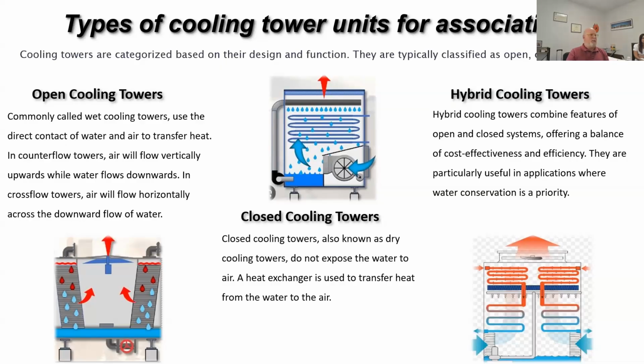It's well beyond the scope of this seminar to discuss the pros and cons of either. Short of that, if you're changing from a cross flow to a counterflow or counterflow to cross flow, it's worth having the discussion and knowing to raise that question with your designer to make sure that if they're changing the type of tower, that they look at various things. For example, one of the things we have to look at is water, especially right on the coast. The water carryover can be an issue with certain types of towers that we need to take a look at.